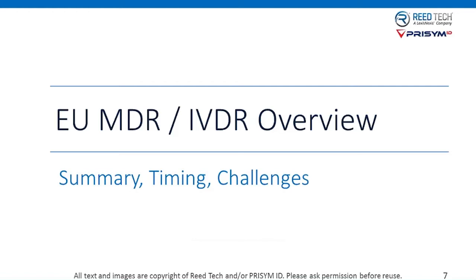So I guess the first question is, what exactly is EU MDR? Basically, it's a new set of regulations which the European Commission is introducing. They're repealing a number of previous medical device directives. Directives are slightly less stringent and slightly less strict than regulations. Regulations pass into law immediately once they're applicable.